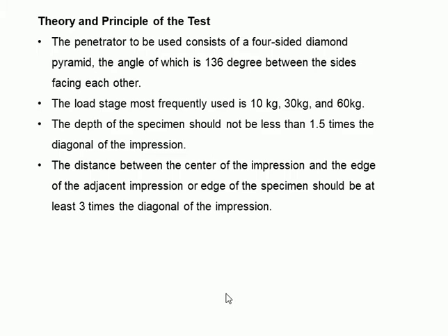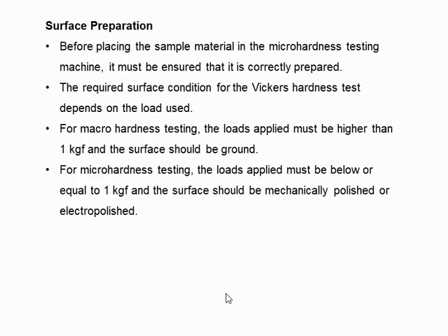The depth of the specimen should not be less than 1.5 times the diagonal of the impression. The distance between the center of the impression and the edge of the adjacent impression or edge of the specimen should be at least 3 times the diagonal of the impression.